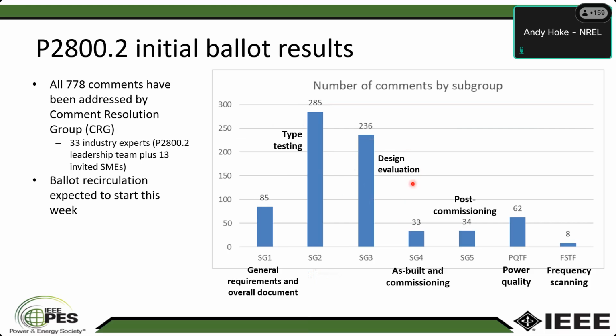And then, as we talked about, the design evaluation comes next, where you evaluate the whole plant design and make sure the plant as a whole conforms with 2800. So those are the two groups, the type testing and the design evaluation, that got most of the comments. There were a handful of comments in other areas on the commissioning and as built, a handful on power quality, and there's actually a frequency scanning group. So actually, we haven't talked too much about this, and maybe some others have in this forum, but as part of type testing, there's frequency scanning that goes on to make sure that the dynamic aspects of the model match the dynamic aspects of the hardware. So anyway, you can see the hot topics there were type testing and design evaluation.